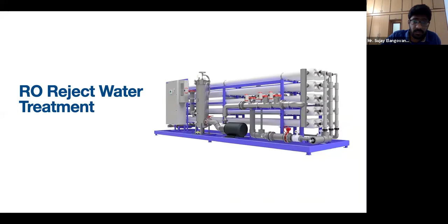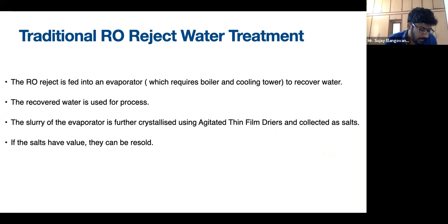So the last case study for today is the RO reject water treatment. The traditional RO reject water treatment is to feed the reject into an evaporator, which requires a boiler and cooling tower to recover water. The recovered water is used for the process directly. The slurry of the evaporator is further crystallized using agitated thin film dryers and collected as salts. If the salts are valued, they can be resold, or they are disposed of in the landfill.